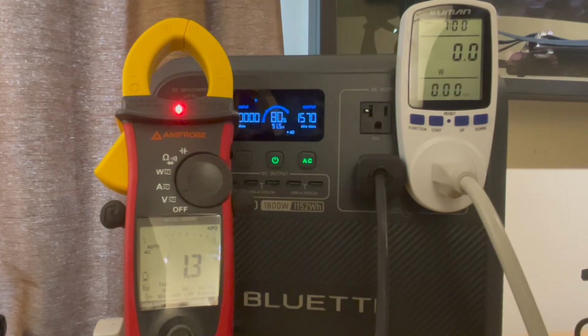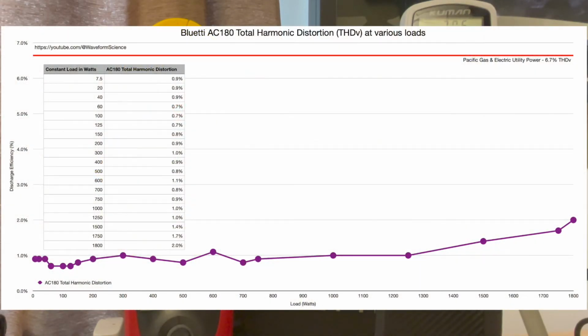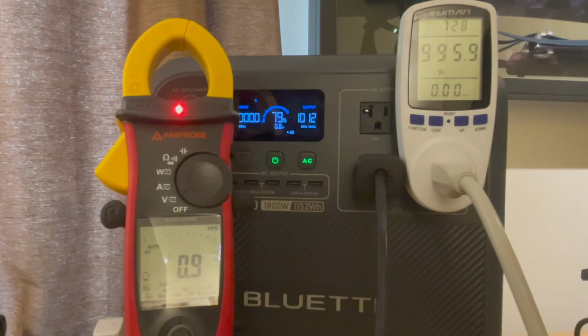Looks like we can push it up to about 2400 watts with nice, clean harmonic distortion. For your enjoyment, I made a harmonic distortion graph across the various loads. Harmonic distortion does increase slightly as the loads go up within the bounds of the readings, but compared to utility power, this is far cleaner power than anything you're going to get out of your utility. So very nice, very wonderfully clean inverter.